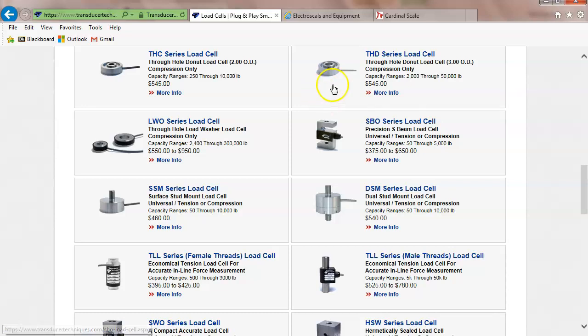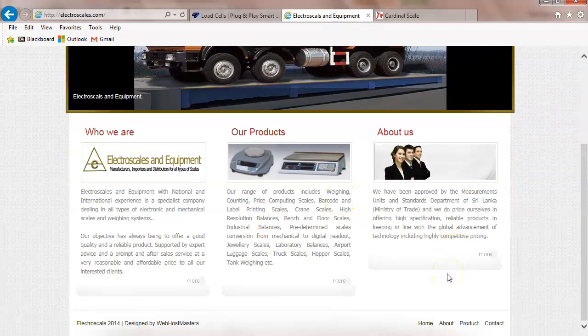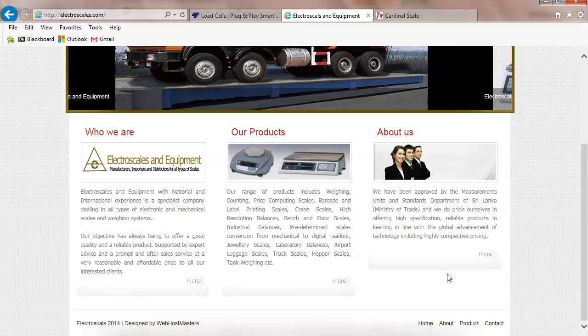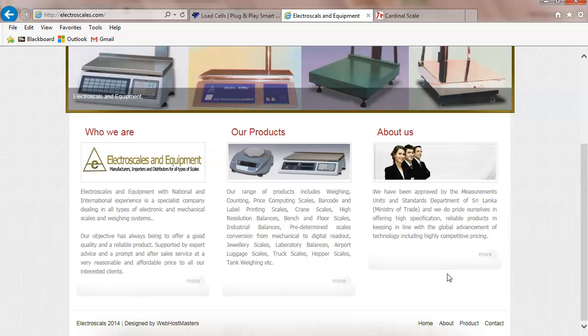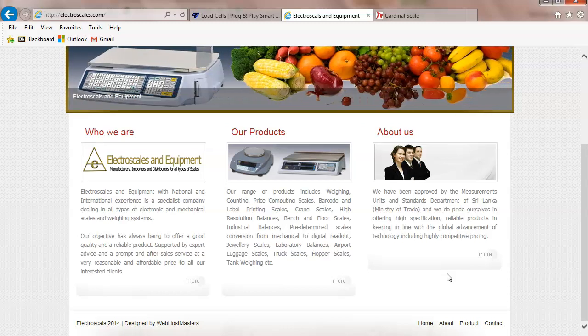The 2 scales that I used to work on, Electric Scale, they're still in business. So these are the actual indicators. Electric Scale was a scale that they bought that didn't have an auto receiver circuit on it. So what would happen is these big trucks would come in there with all that lime. They'd spill a little bit on the scales, and the weight would go up, right? You understand?